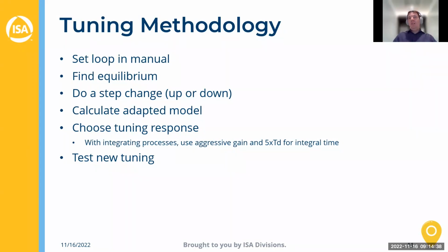Yeah. No, because let's say you do your test with the filters removed and then you add your filter, you try to do your tuning with the model without the filters. It's all part of your process response. So I'm not talking about the VFD here, but of course it will affect your tuning. You don't want a controller asking to move faster than the VFD can handle, right? Then you will have a mismatch between what you're expecting the response to be and the real process response. But in this case, you would still have your dead time regardless of that. You may just not have a sharp break like I had. You may have a small ramp, but you still can estimate the dead time when the pump starts moving.